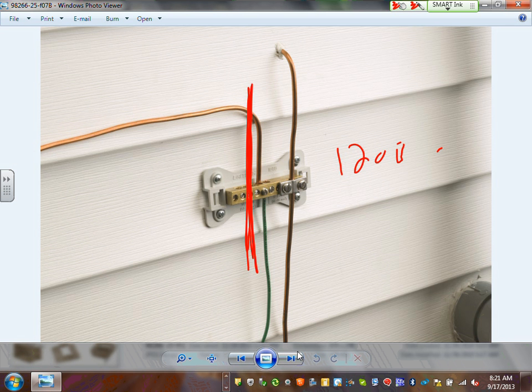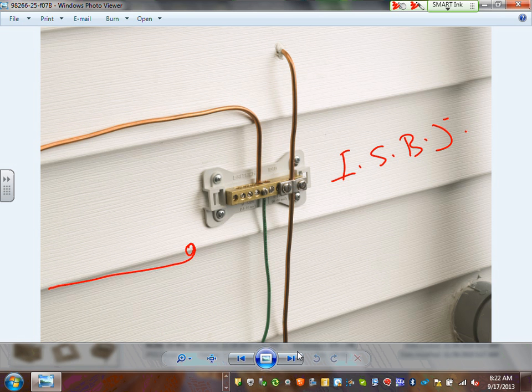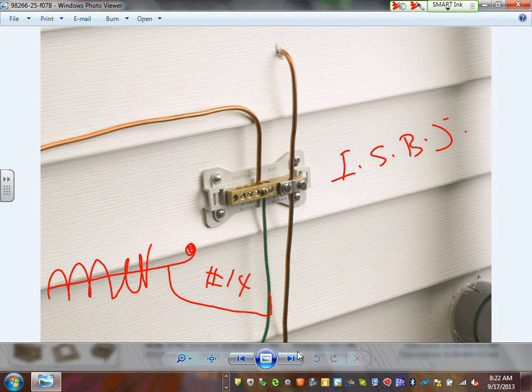Okay, when you bring your coaxial cable, guys, this is called the inter-system bonding jumper. As your coaxial cable comes into the building, I'm going to show my coaxial cable coming in here and terminated to the building. You have to bring that number, I think they use number 14, and the shield, can you guys see that? The shield of the coaxial cable must come into this terminal. This is called the inter-system bonding jumper, required by code, right by the meter equipment or the main service equipment.